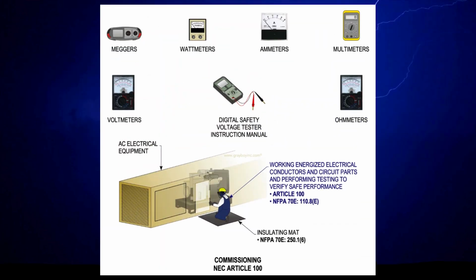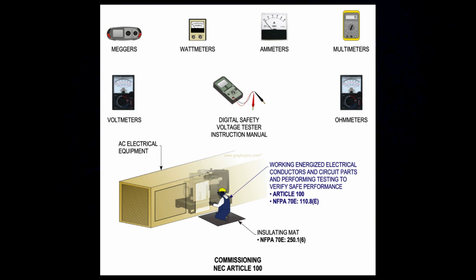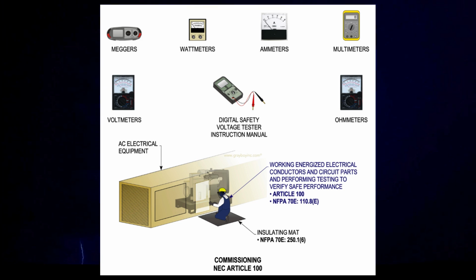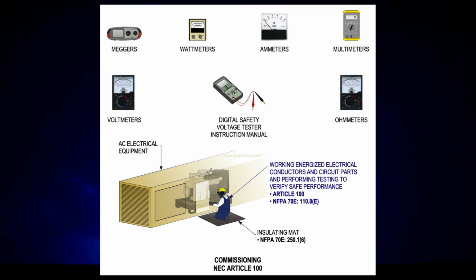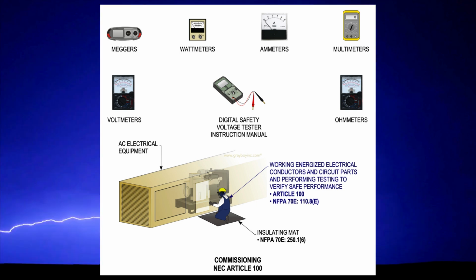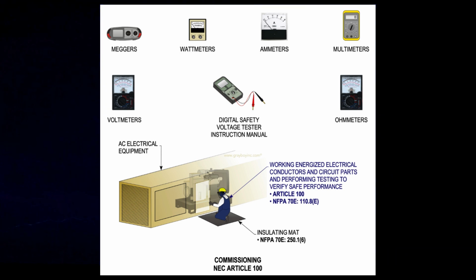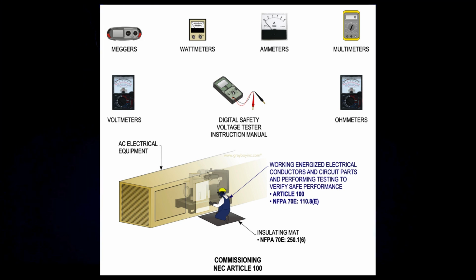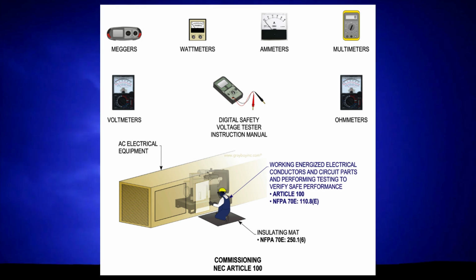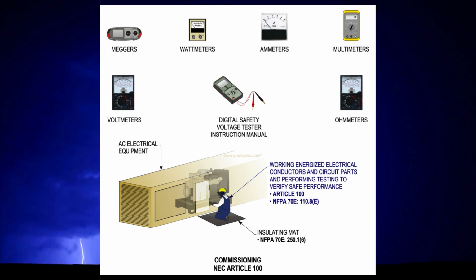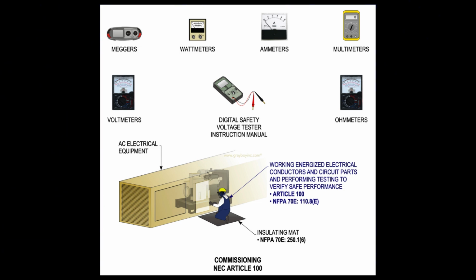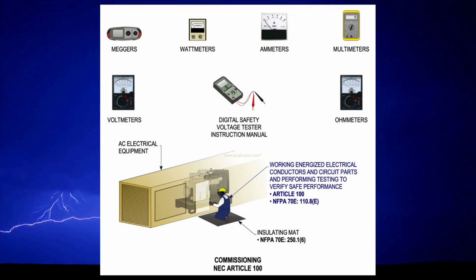A revision has been made to clarify that the commissioning of electrical devices and systems are paramount to ensure a safe installation. When commissioning electrical devices and systems, this often includes special setup steps to adjust device and system settings, performing verification tests, interlock and safety system, operational performance, and validation of the sequence of operation.